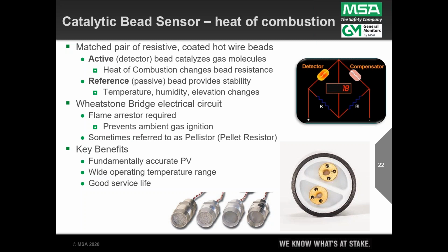That's fundamentally accurate. In fact, the ISA standard requires manufacturers like MSA and anyone, if the device is going to be approved to the standard, which they have, to be accurate to plus or minus 3% of applied gas concentration from 0 to mid-scale, and then plus or minus 5% of applied gas from mid-scale to full scale. So it's really amazing that these devices are that accurate. And they have a wide operating temperature range. In fact, if it's a high temp application where you're above the temperature rating of your 32-bit processors, this is a great way to go.